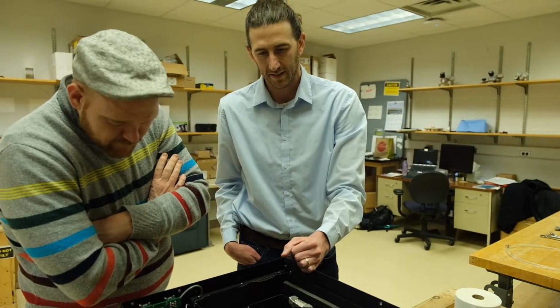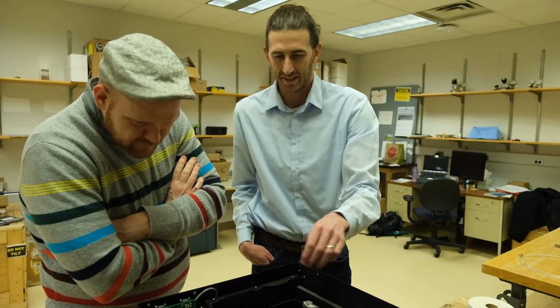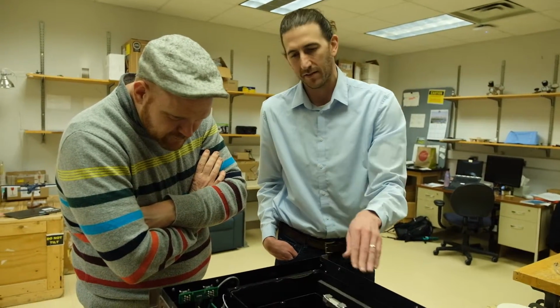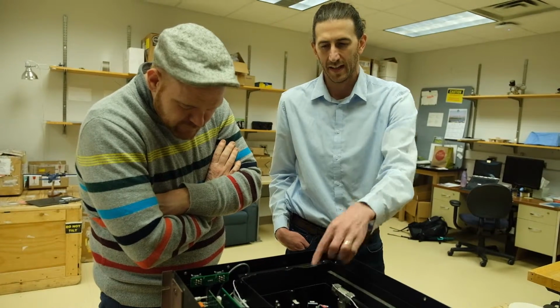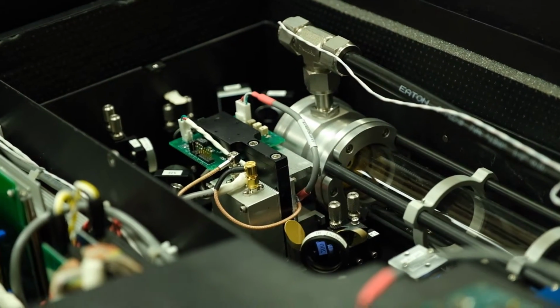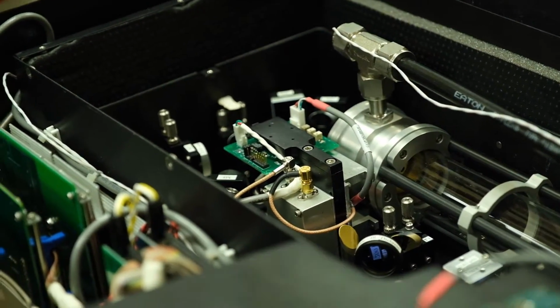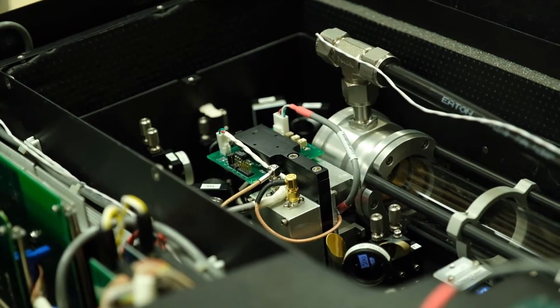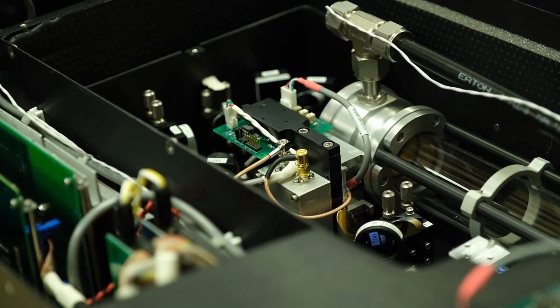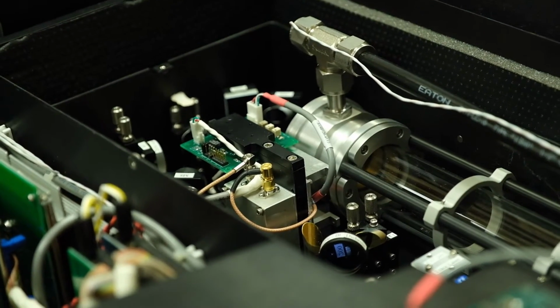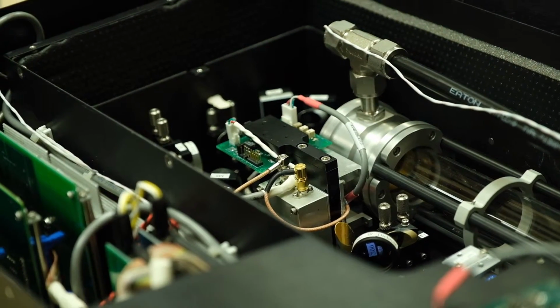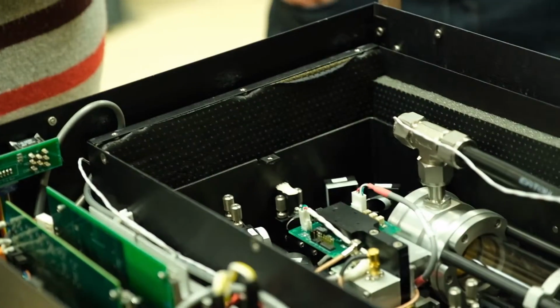There's a couple of subtleties over here. There's a cell that oscillates into the line that has some of the gas of interest, so that you can make sure you know what wavelength you're at. And then there's a thing called an etalon, which lets you know, as you tune the wavelength of your laser, how rapidly you are changing the wavelength. The way we change the wavelength is actually by changing the temperature slightly. It changes the wavelength that's emitted a little bit. It's a very small range.